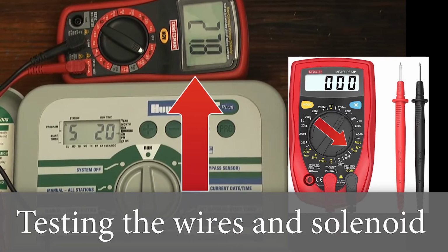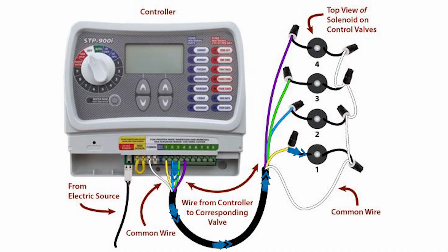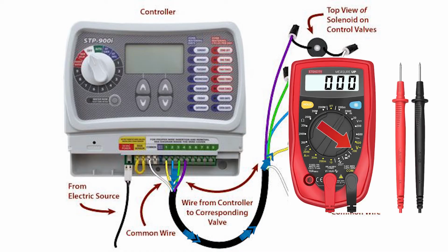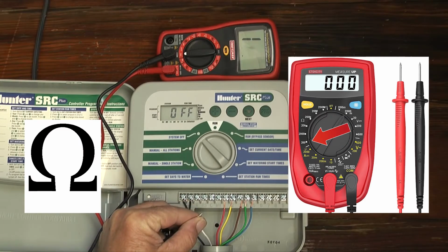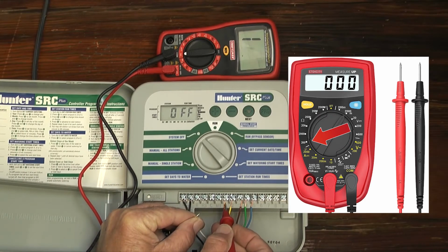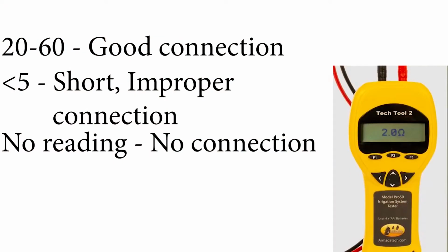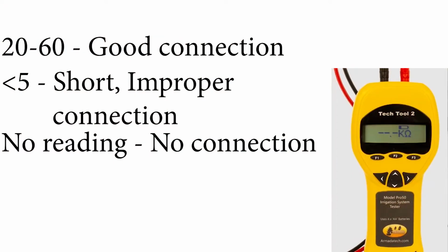Testing the wires and solenoid. To ensure electricity is traveling between the timer and the solenoid, leave the multimeter connected the way that it was and select the omega sign, which stands for resistance. If the reading is between 20 and 60, there is power traveling back and forth from the timer. If the reading is below 5, there is either a wire damaged or connected in the wrong place and it's shorting out.